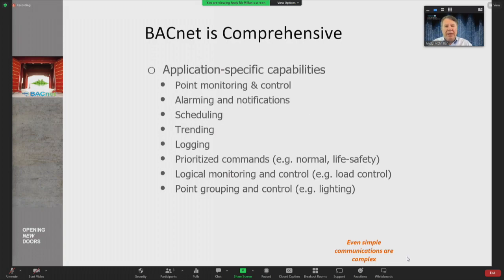And then BACnet is comprehensive in one more dimension: application-specific capabilities. Along with those devices and being able to communicate messages, it specifically addresses how you identify points and monitoring, what alarming looks like, notifications, scheduling, trending, and logging. These are designed into parts of BACnet to address all of these.